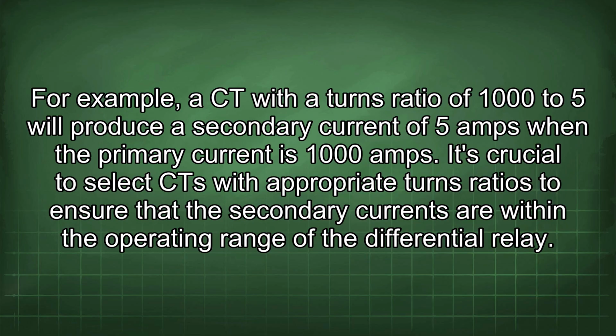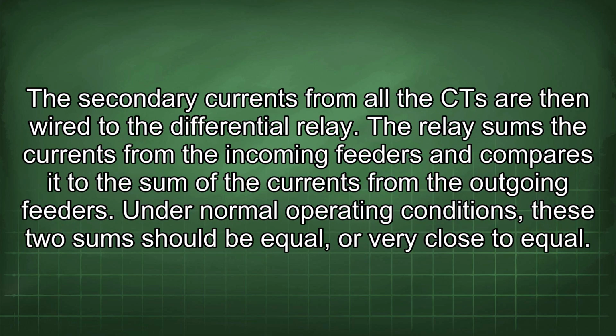For example, a CT with a turns ratio of 1000 to 5 will produce a secondary current of 5 amps when the primary current is 1000 amps. It's crucial to select CTs with appropriate turns ratios to ensure that the secondary currents are within the operating range of the differential relay. The secondary currents from all the CTs are then wired to the differential relay. The relay sums the currents from the incoming feeders and compares it to the sum of the currents from the outgoing feeders. Under normal operating conditions, these two sums should be equal, or very close to equal.